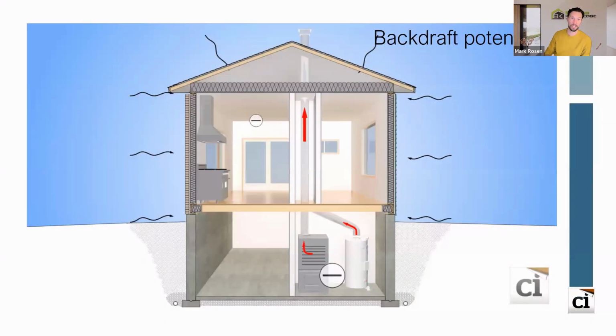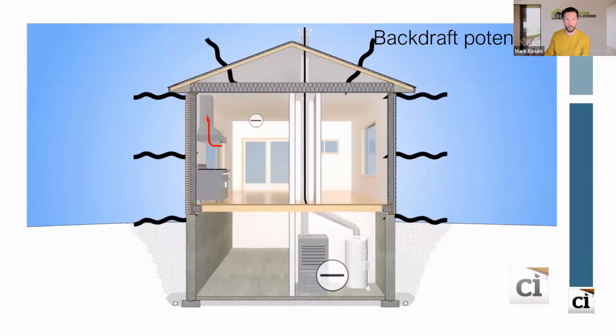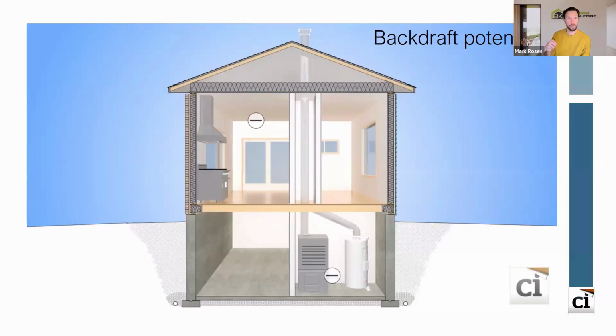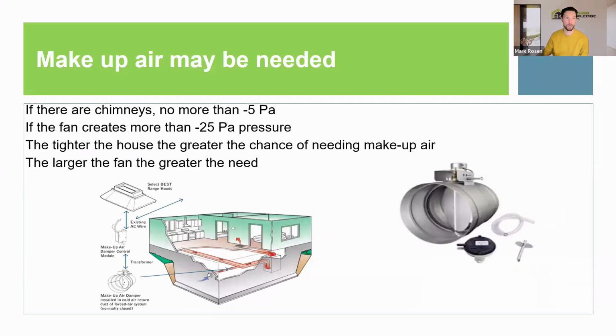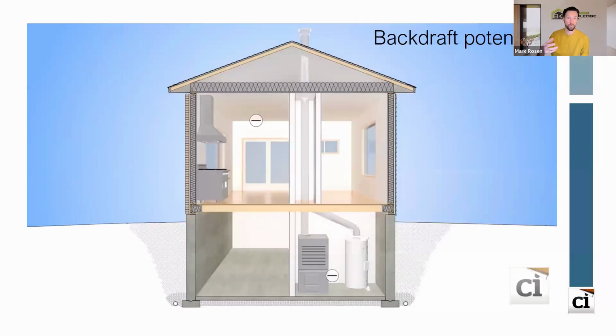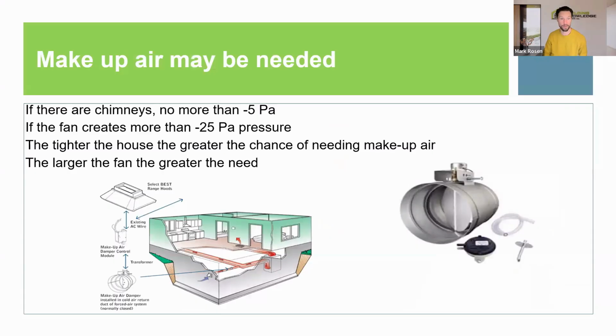We also have to be aware that in some older homes, when retrofitting and dealing with older hot water tanks or furnaces with open combustion venting, if we don't measure the depressurization caused by that range hood and other fans in the house, we can actually work against those vents and backdraft them—meaning the combustion air from the hot water tank would stop going up the flue and start coming into the basement, which could be a major health risk.